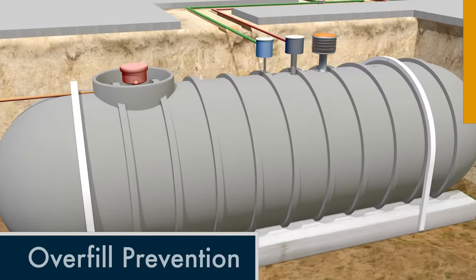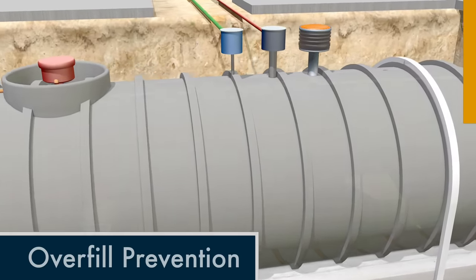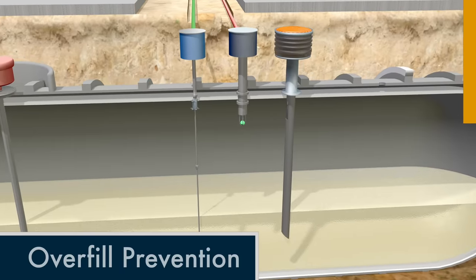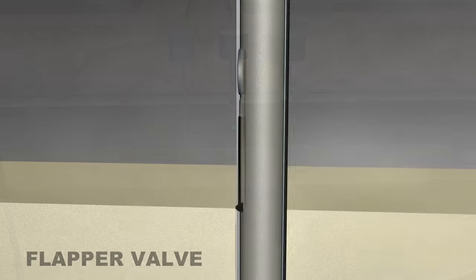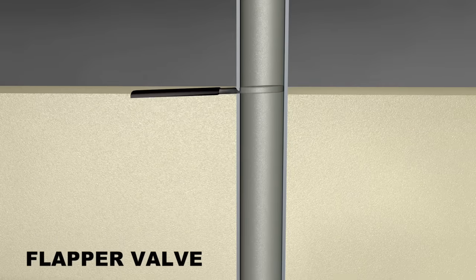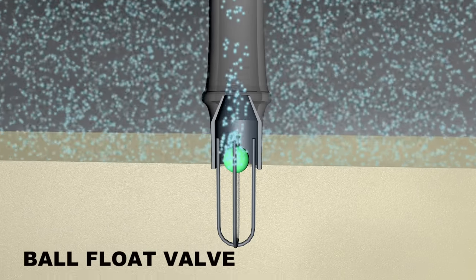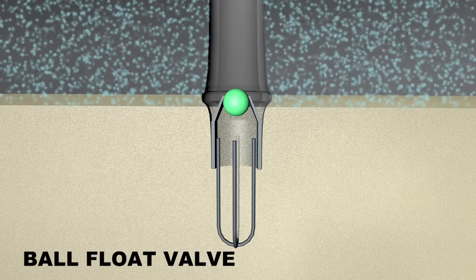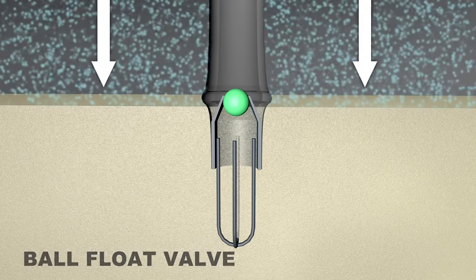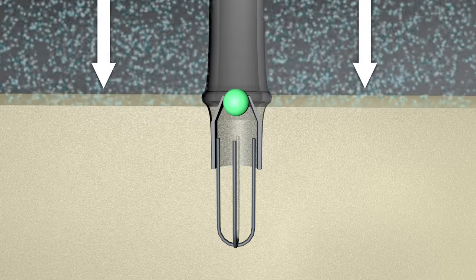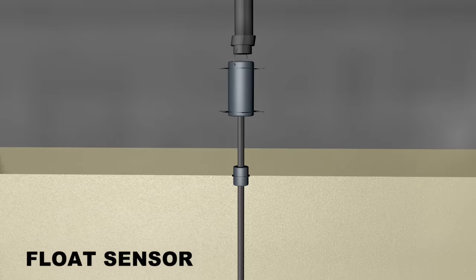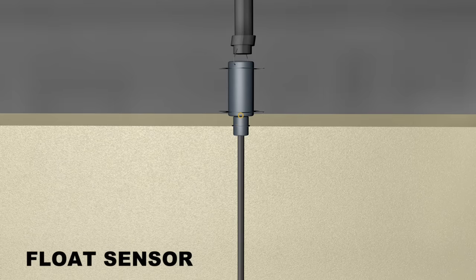As an added measure of safety, today's underground tanks feature a variety of overfill prevention technologies. A flapper valve automatically cuts off the flow of fuel into the tank, while a ball float in the vent pipe prevents vapor from escaping. The pressure of vapor within the tank then prevents additional fuel from entering. A float sensor alerts the operator if fuel reaches the target level.